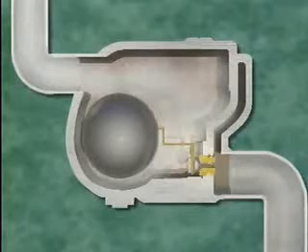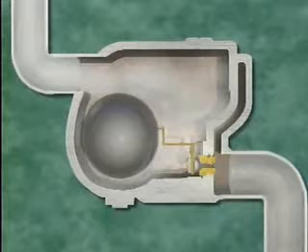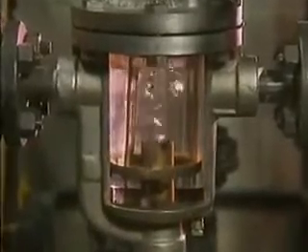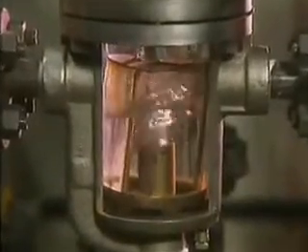Steam traps must also be able to remove air and non-condensable gases that could build up in the trap and keep it from working. Air and other gases also make a trap more susceptible to corrosion. For example, carbon dioxide is one of the most common non-condensable gases in steam systems. When carbon dioxide mixes with condensate, carbonic acid — which can corrode metal pipes and trap components — is produced.